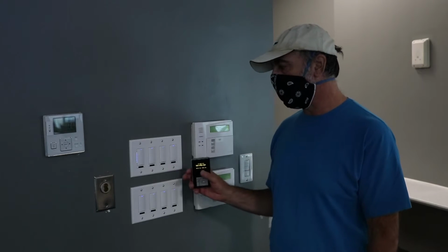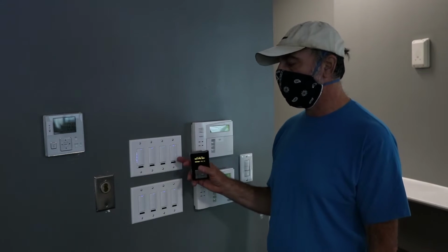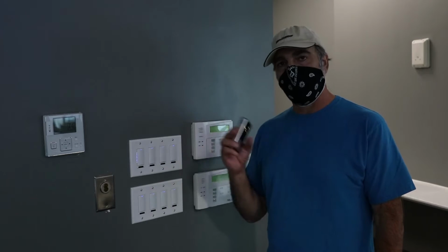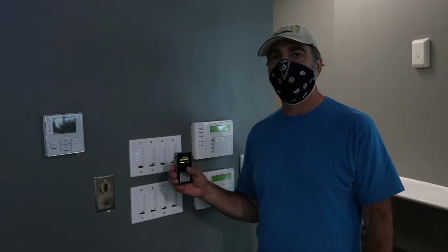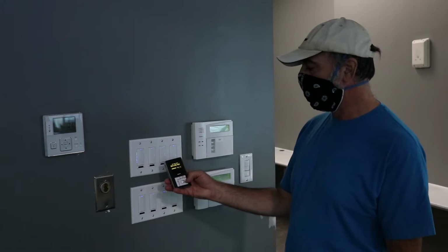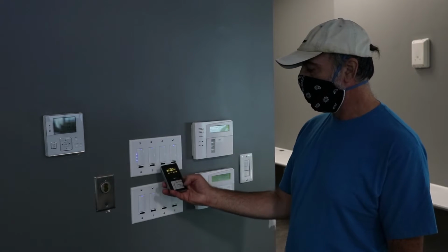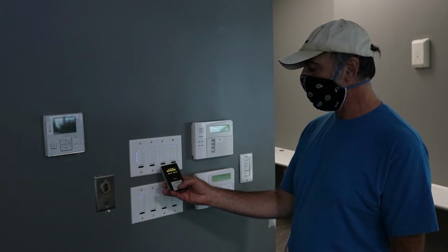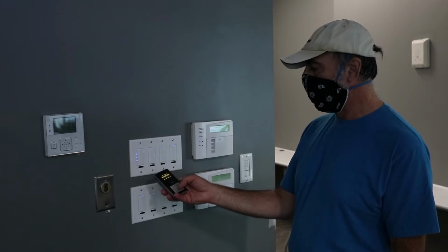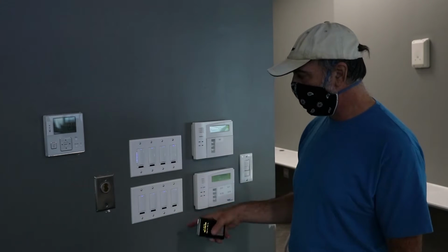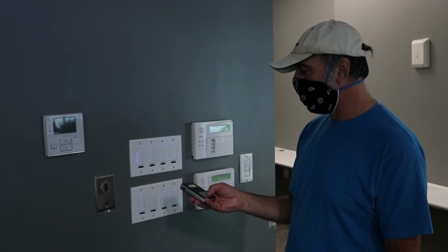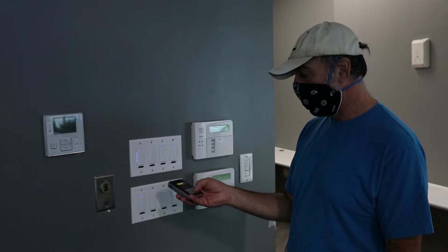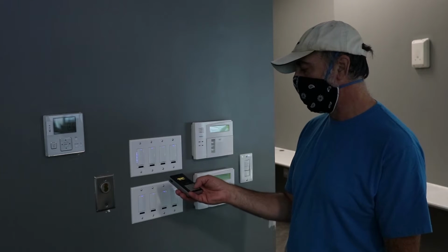What the after hours is, that actually happens in real time at 8 p.m. It turns the lights off, but then all the switches are enabled, so anyone could turn the lights on and off. So I'm going to switch this over to after hours. So I use the left and right arrow. Then I press the center button. I could aim it at any one of these IR little windows. This is an IR remote. And then it tells me to point at any IR device.